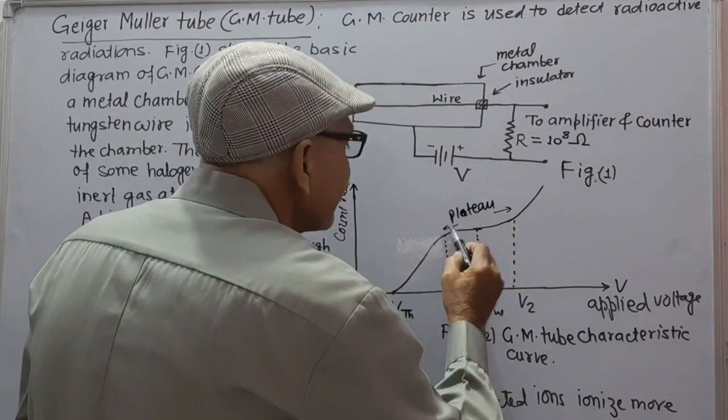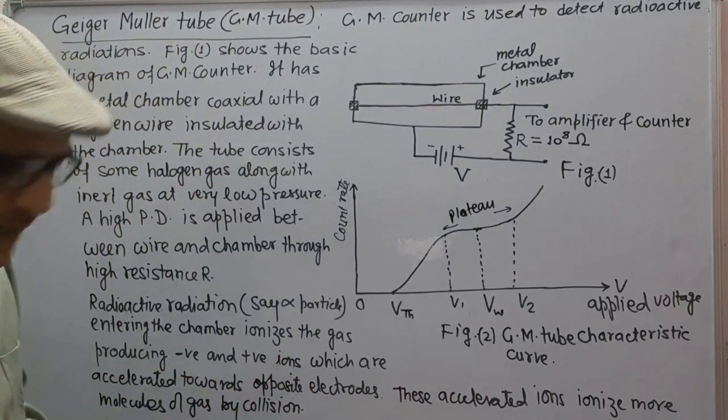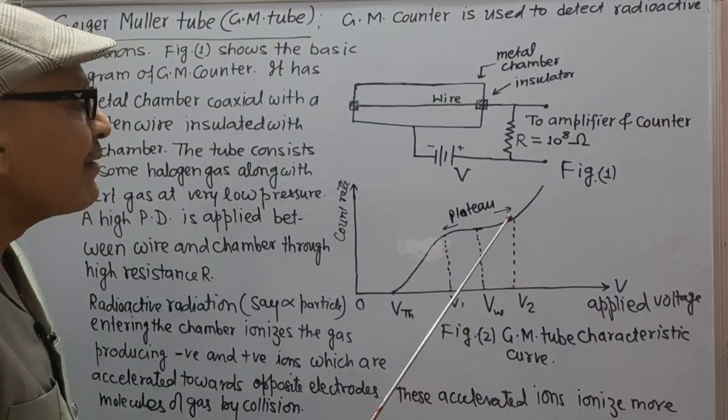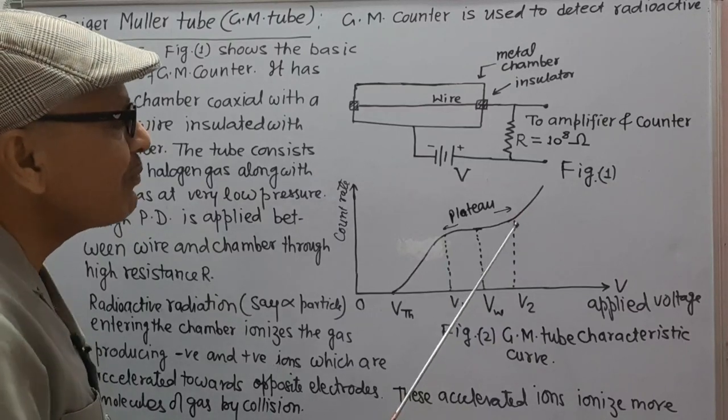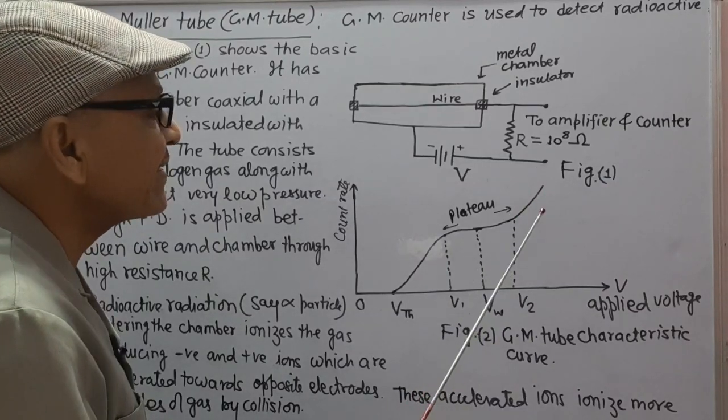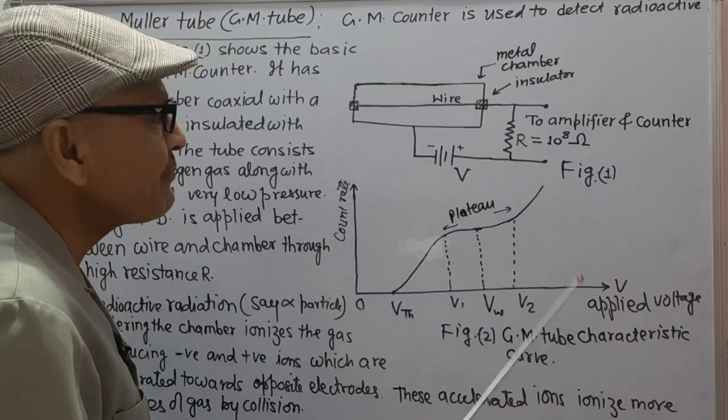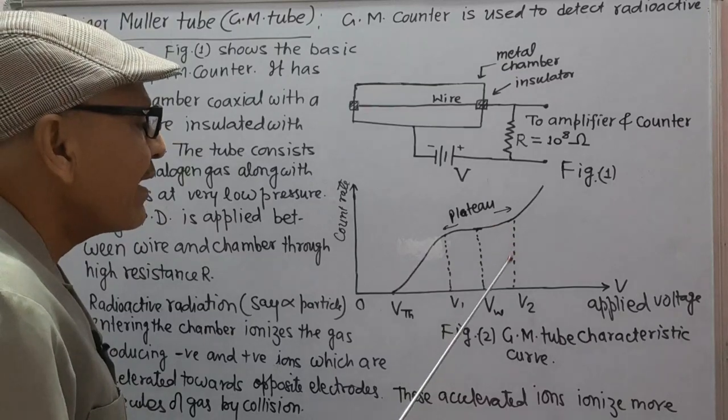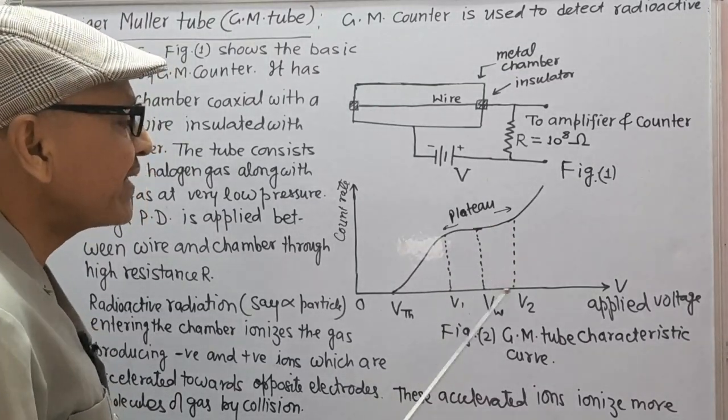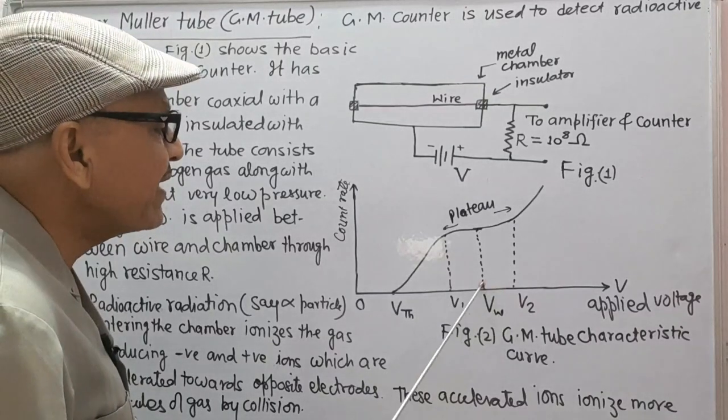Now the count rate suddenly increases up to point V1. Then a plateau comes from V1 to V2. Beyond voltage V2, the count rate suddenly increases which may damage the GM tube. Therefore, the best operating voltage is the mean of V1 and V2 at voltage VW.